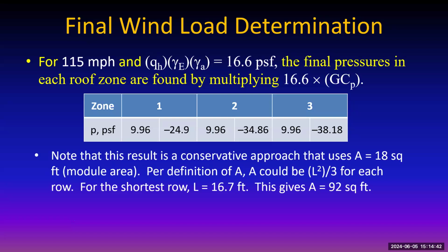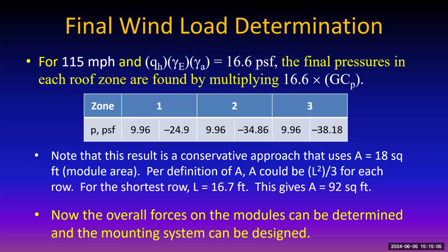All right, that's our conservative approach. And that uses A is equal to 18 square feet per module. But here's a little note that I made about A. It could, in fact, be L squared over 3, and it could give A of 92 square feet for the array that we have, the smaller, shorter row. But it depends on how confident you are with that.